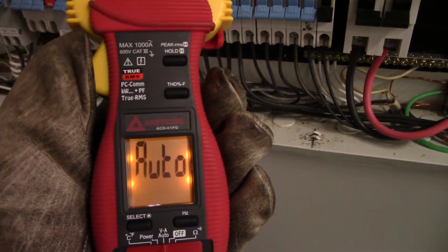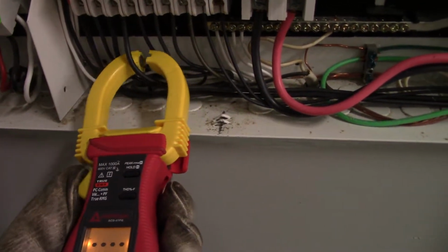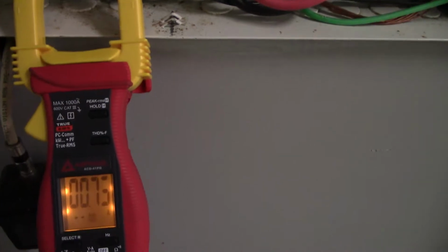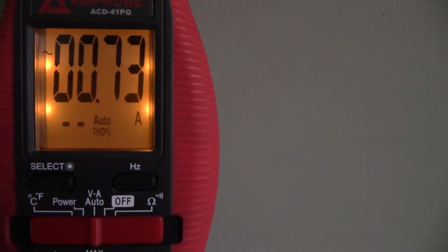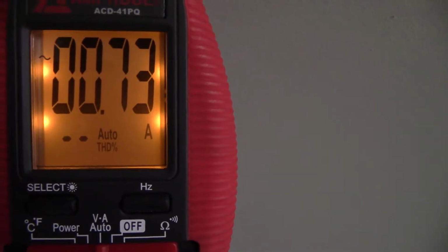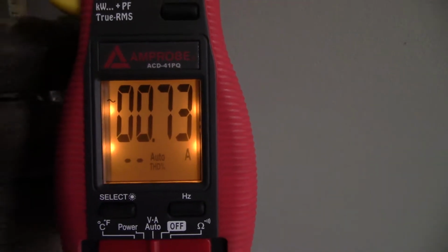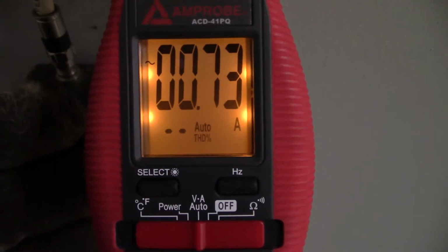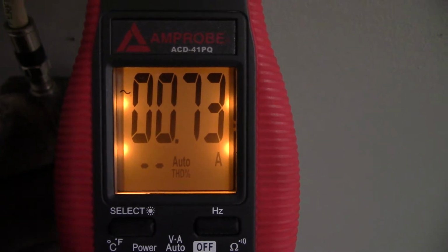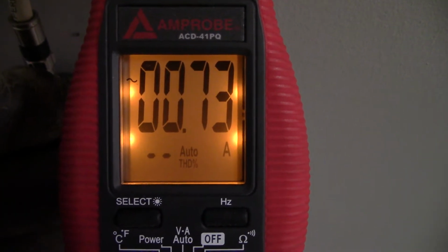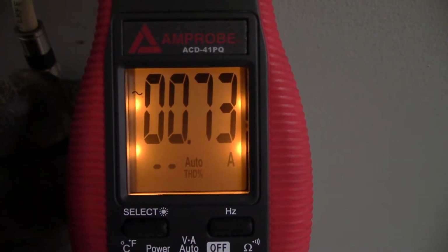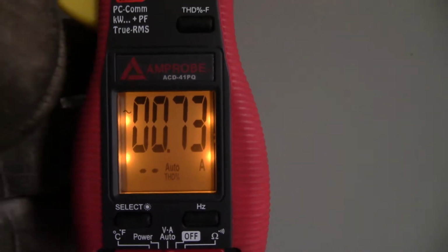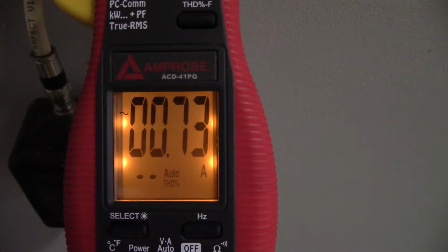So we'll take this meter and we'll clamp it on to that circuit. Now, what you're going to notice though, and this is important when you're working with this meter, is you can see that we've got about 0.73 amps of current flow, but it doesn't have a reading for distortion. Now, there's a reason for that. That is what we call a split screen, where we can read the current and distortion, but it will only read up to 100% distortion. This meter will read up to almost 1000% distortion.